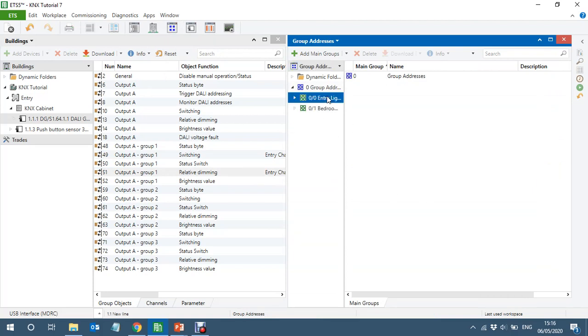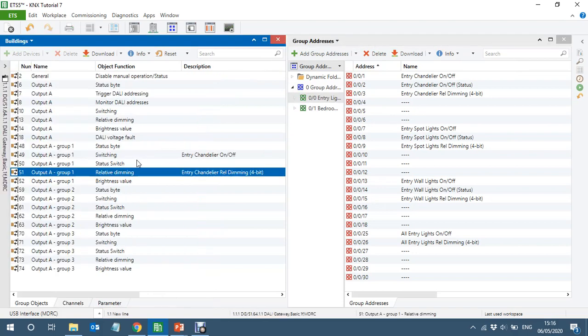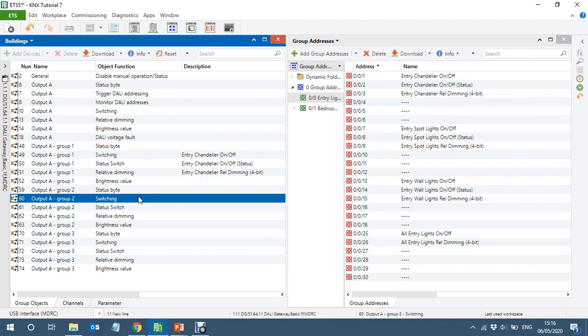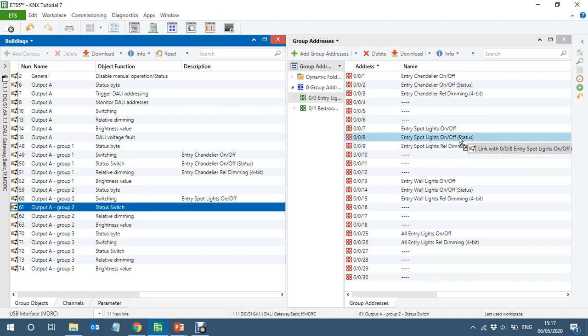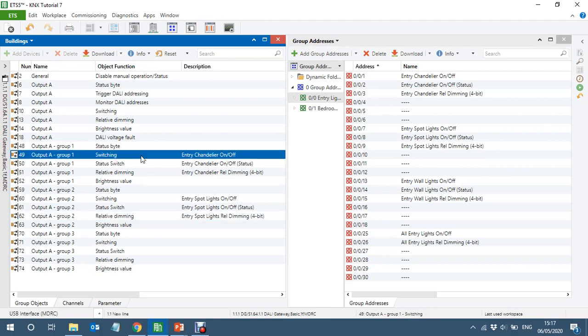Entry lighting, so we have chandelier, exactly the same thing, switch status and on and off, switch status dimming, and this one if you want to send a specific value of percentage value. The same thing you link with, let's suppose the spotlight is also, entry spotlights are also DALI lights. So what I will do, create groups here, switch status and relative dimming. Now this is group two here. Entry spotlights I have linked it to group two, and the chandelier into group one. So remember I've done it in chandelier in group one and spotlights in two. Let's suppose we have four or eight spotlights and one chandelier somewhere on the job.